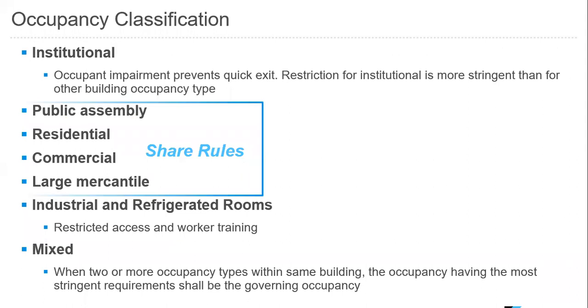Those main classifications include institutional, public assembly, residential, commercial, large mercantile, industrial and refrigerated rooms, and then mixed. And mixed is when we have 2 or more occupancy types within the same building. So what we'll do is apply the rules to the occupancy that has the most stringent requirements.